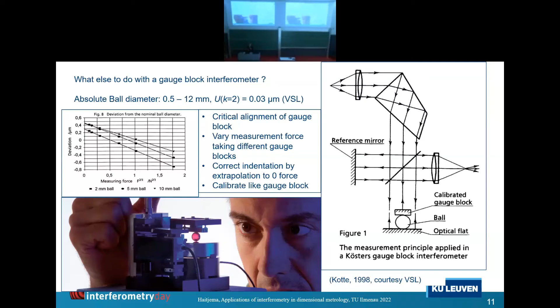Then the other things, I must say, if you look in the world of dimensional metrology, there are two kinds of laboratories. The one has one box of gauge blocks, and they do everything with it. They calibrate every instrument, whatever. The other type of laboratory bought a very expensive laser interferometer, and then they think, well, if I have such a thing, I must use it. So they try to do everything with the laser interferometer. In laser interferometers, as the previous speaker already mentioned, there are homodyne systems, heterodyne systems. The good thing is, in the end, they all count fringes, and they all have a fraction. And the manufacturer of the one type can exactly tell you what's wrong with the other type.